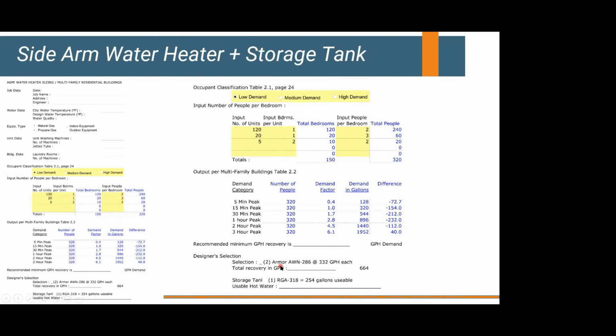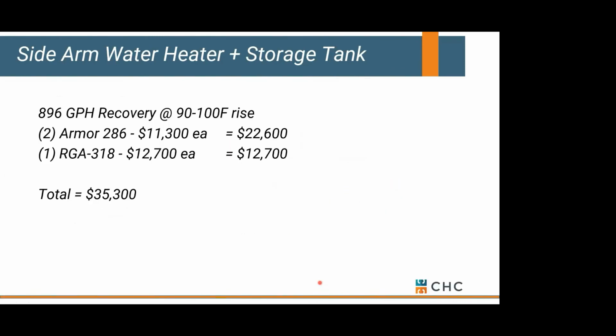So what we've done here is we've selected 2 condensing water heaters that produce a total of 664 gallons per hour. But I'm still short 232. Well, how do I make up for that? With the storage tank. So in our case, we're using a 318 gallon storage tank, but I can't use all of it. Okay, I can use about 80% of it, which gets me to 254 gallons of usable, which exceeds my 232, which tells me that this is going to work just fine. Now this is where you can play with a small heater, large storage tank, large heater, small storage tank, depending on how you want to approach it, and depending on how much room you have in your mechanical room. Okay, if I look at this example, sidearm heater with a storage tank, total for the heaters and the tank, I'm in at about $35,000.